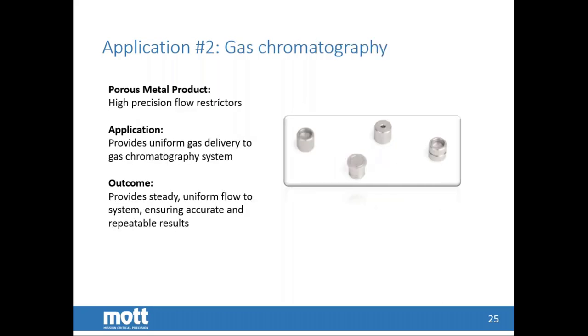For gas chromatography, primarily it's restrictors that are used to control the gas flow rates. The advantage is it provides a uniform gas delivery, so you get a steady uniform flow to the system ensuring accurate and repeatable results.